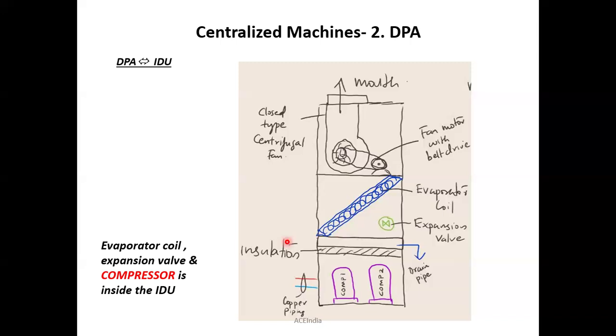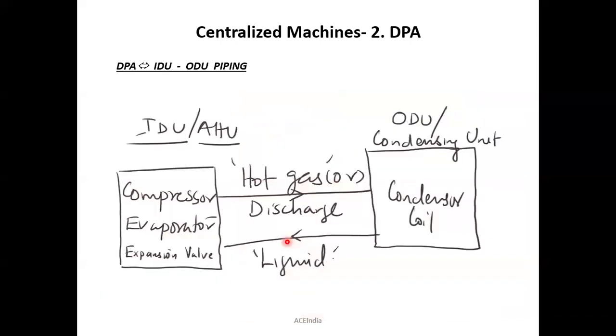Am I right? It's a superheated vapor. That's why those lines, especially on DPA, the copper pipe connection which connects from a compressor to condenser, that means IDU to ODU, that is compressor to condenser, should be termed as hot gas line. Why? Because it's a high pressure and high temperature in a gaseous state itself. Okay, now that's why it is termed to be hot gas line. Then the other connection is still the same, this liquid line itself. All right, from condenser coil to expansion valve.